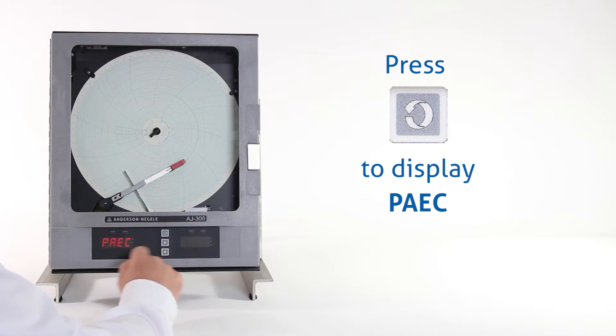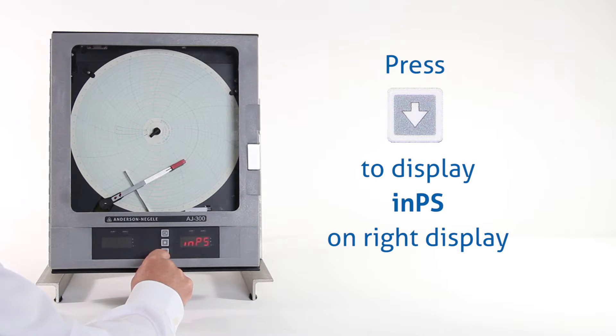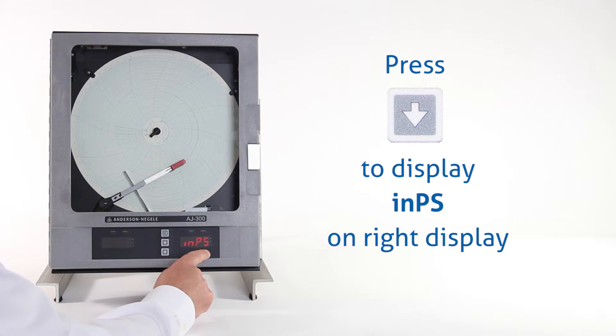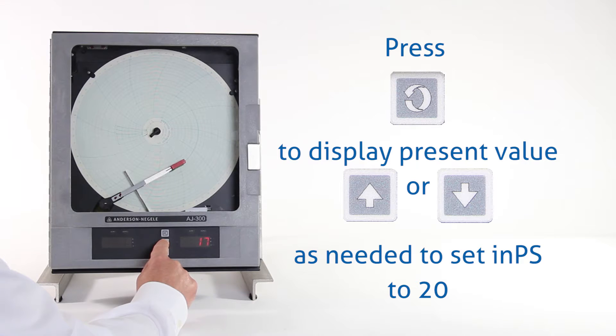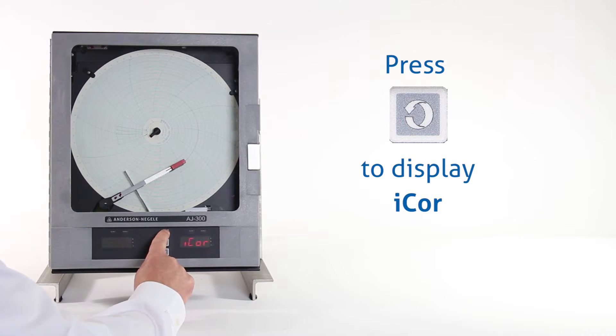We'll see PAEC on the left display. Now we use the down arrow key to get over to INPS on the right-hand display. Once we have INPS, we hit the scroll key, and again we want this number to be set to 20 for RTD input degrees C. We use our up arrow key to get to 20. Once that's at 20, we hit the scroll key one time and we have ICOR.